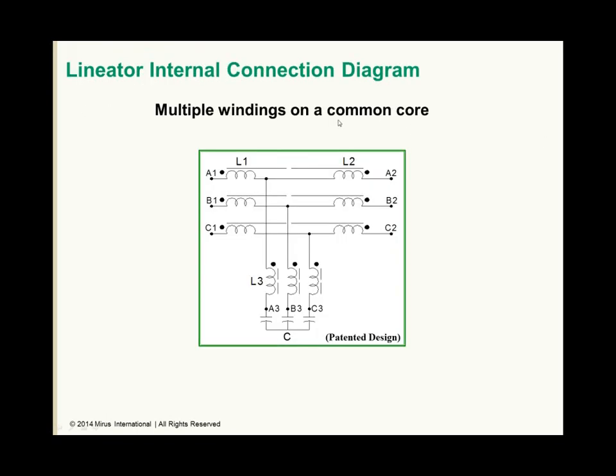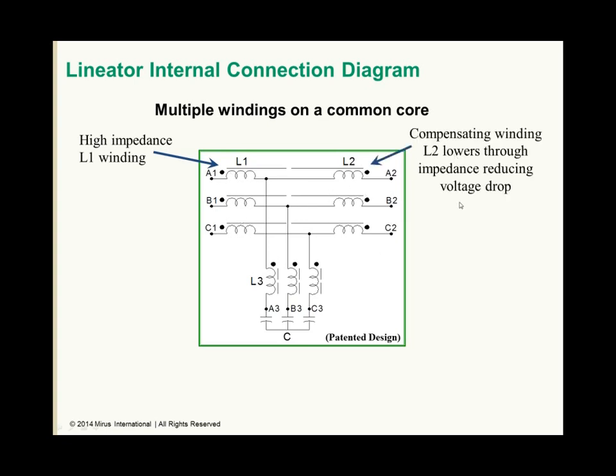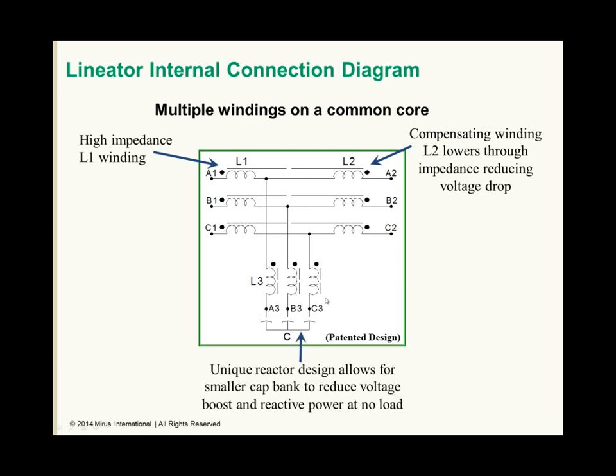The connection diagram of the Lineator passive filter is shown here. We have a blocking reactor, with very high impedance, on the input. We have a compensating reactor on the output where the load is connected. And we have our branch reactor, which combines with our capacitors to produce our tuned frequency. This unique reactor design allows for a smaller cap bank to reduce voltage boost and reactive power at no load.